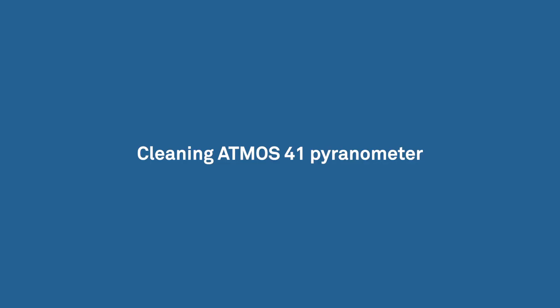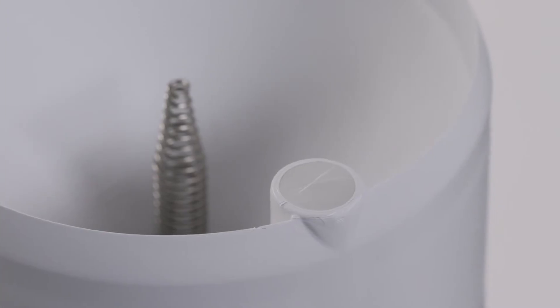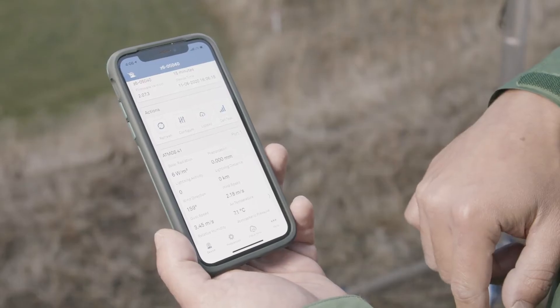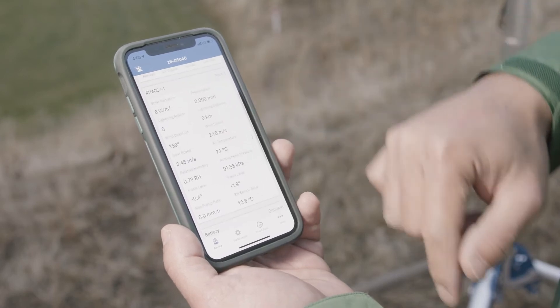To clean the Atmos 41 pyranometer sensor, check the pyranometer sensor regularly to make sure it is clean and has no scratches or gouges. If damaged, contact customer support for a replacement. Check the pyranometer data often to identify possible problems.